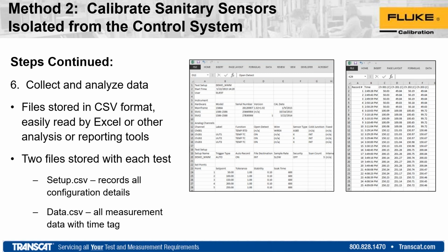So again, it semi-automates the whole process, with the exception of the tweak at the end. During the testing, that's something you probably want to review anyway, just to ensure that there are no skews that look off in your data, no spikes or anomalies that you may want to question, and potentially rerun a test on the particular sensor you might be seeing an issue with.